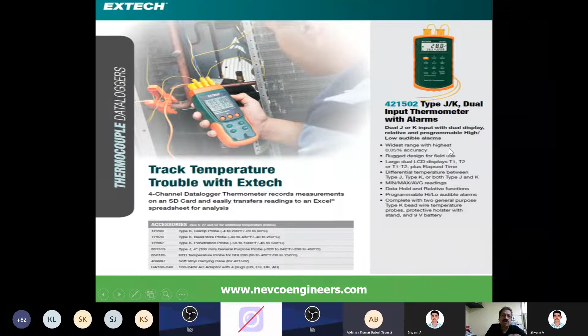You can have a variety of thermocouples used for different applications. Suppose somebody wants to measure the temperature at different places. You can connect 4-5 different temperature probes, and you can collect the exact temperature inside any combustion zone or anything, right? So these are all contact type. This is the display with a K-type thermocouple. You can measure from minus 52 to 1300 degrees centigrade with a K-type thermocouple probe.